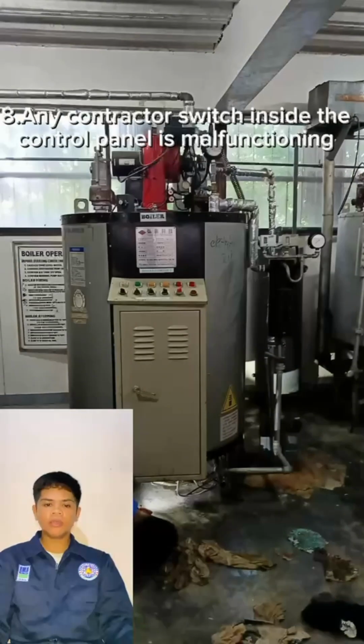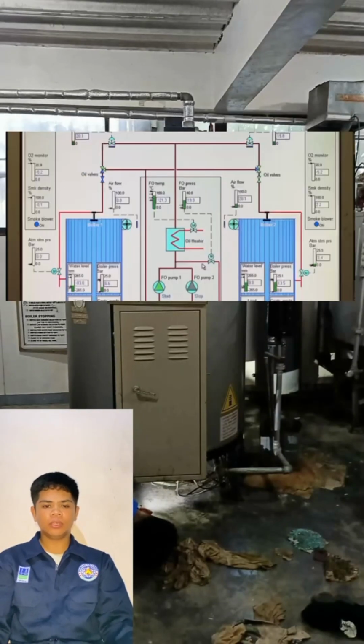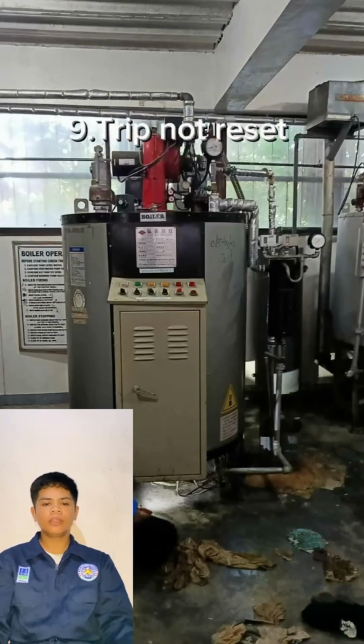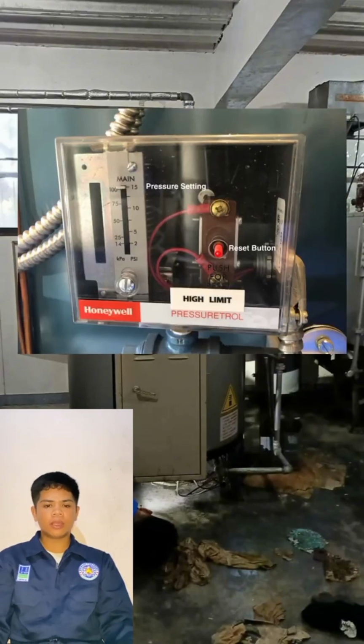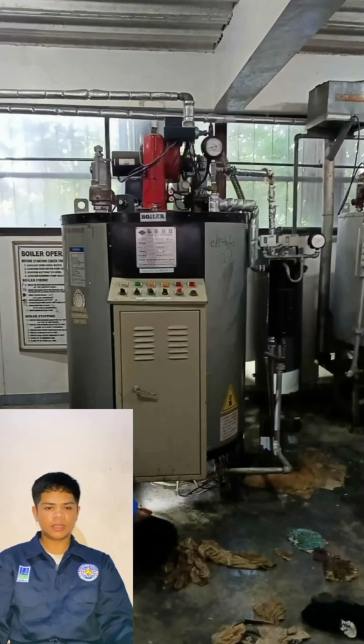The eighth is that any contactor switch inside the control panel is malfunctioning. The boiler control panel consists of several contactors and PLC cards. Even one contactor malfunctioning results in trouble with the boiler starting. The ninth is that a trip is not reset, if any previous trip like low water level, flame failure, emergency stop, and so on.